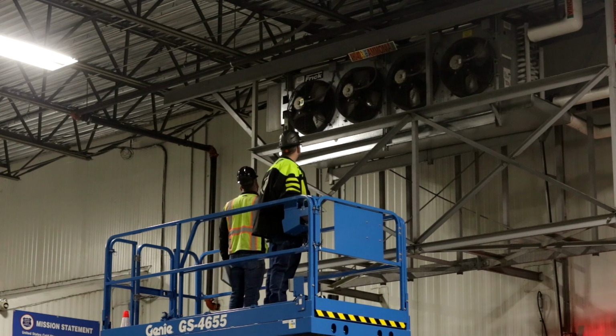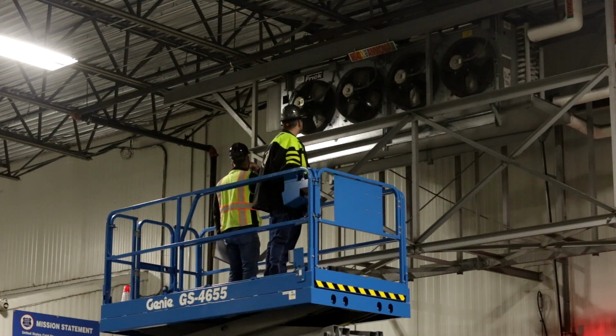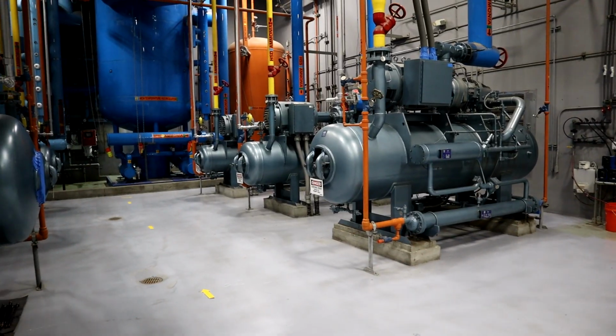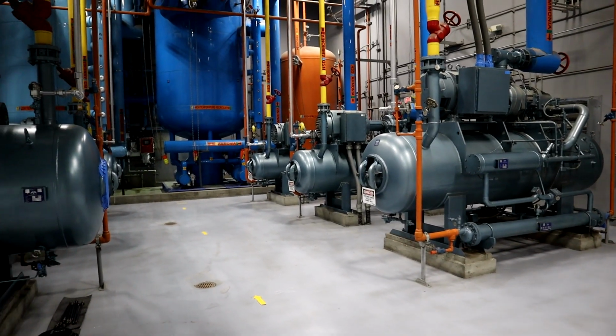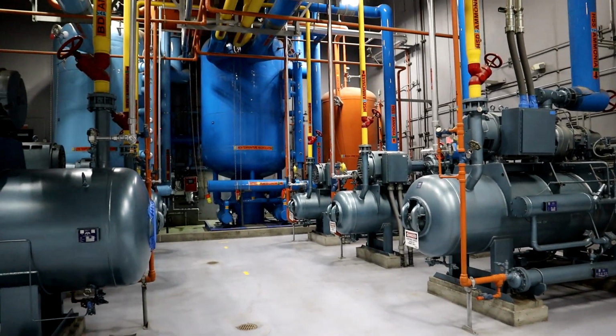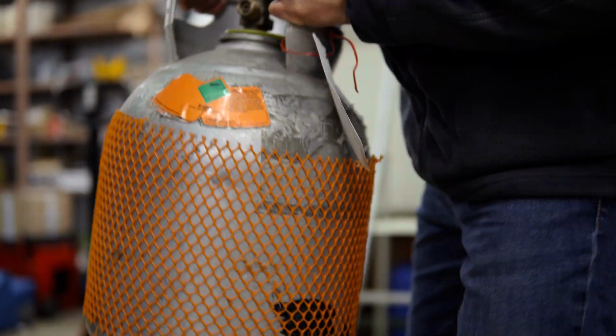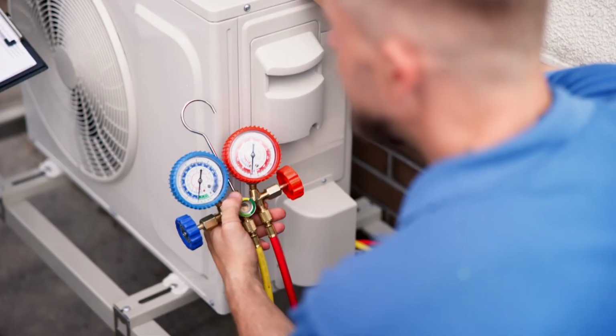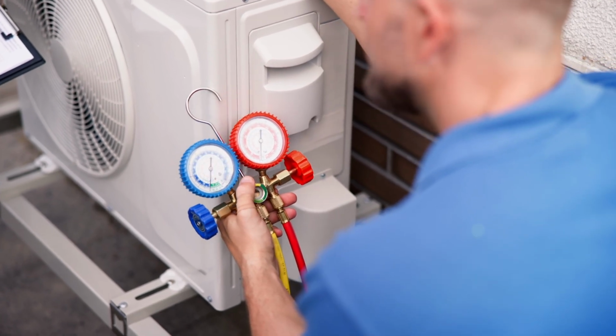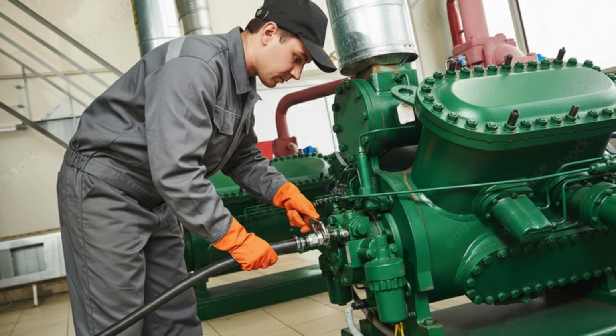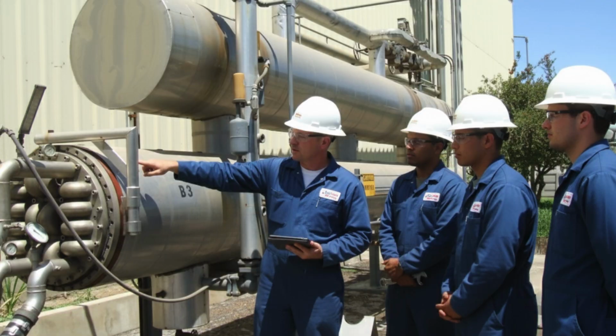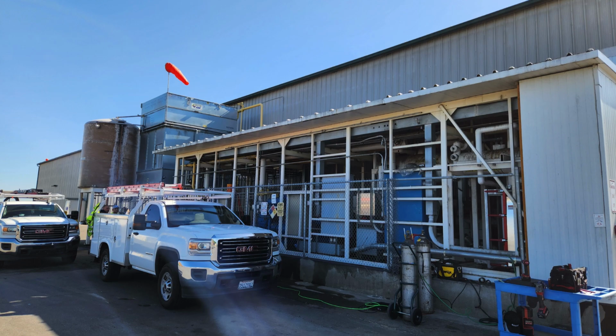One of the primary responsibilities of an operator is to ensure the refrigeration system is operating efficiently and meeting the expected facility refrigeration loads. This is only possible if the system is properly maintained. Therefore, an operator must see to it that maintenance is performed. This might mean that the operator is routinely turning wrenches, that he manages a team of technicians, or that he oversees the contractor providing this essential function.